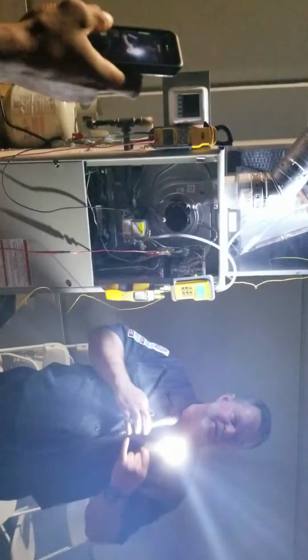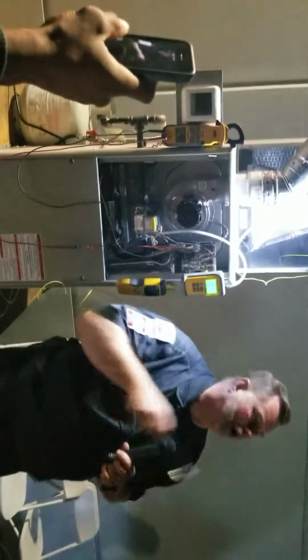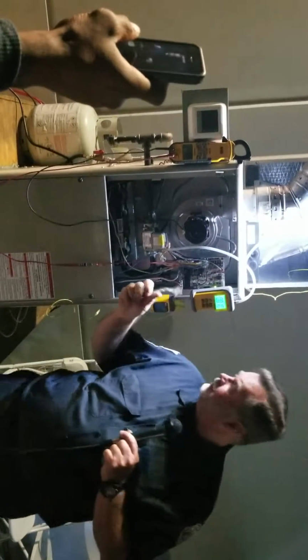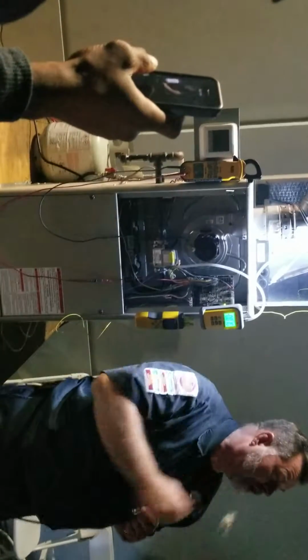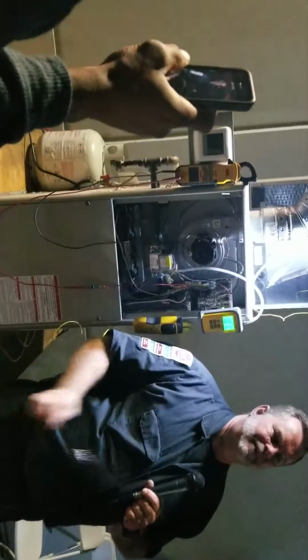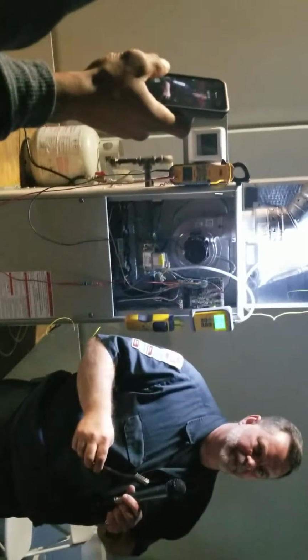Any questions, guys? We've gone through the sequence of operation. We've looked at the flame sensor. Oh, while this is cooling off, I want to say something. When you clean the flame sensor, because the flame sensor does get dirty with carbon because it's in the flame, right? And so you can get particles of carbon on the flame. The way that it works is, it's called flame rectification. The voltage is 120 volts, sending out through this wire to the flame sensor, but it's very low current, microamps. So as the flame goes across that rod, the particles of carbon will convert it from AC voltage to DC voltage because it only allows one side of the sine wave to go to ground. It's called flame rectification.